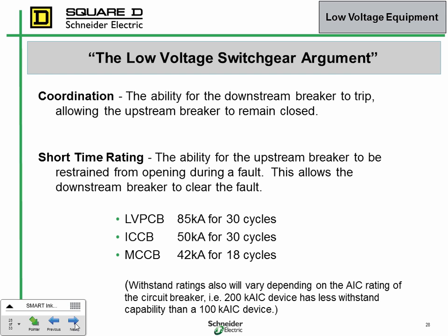Right. And we do have a maintenance switch capability so that you can turn it to maintenance mode. At that point, basically all the settings are pretty much reduced down to minimum, and then your exposure categories are in that one or two area. If it's a service entrance gear though, you're still dangerous, in standard switchboard construction anyway, because the busing's wide open in the back. So that fault could propagate through the entire lineup. If the problem is your cables on the incoming, the only protection they have is on the medium voltage side of that transformer.